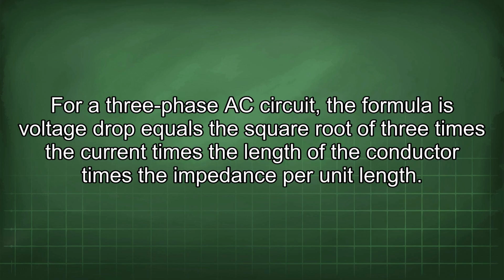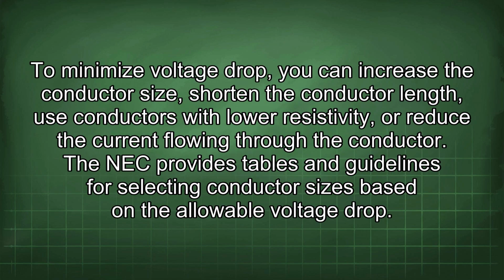For a 3-phase AC circuit, the formula is voltage drop equals the square root of 3 times the current times the length of the conductor times the impedance per unit length. To minimize voltage drop, you can increase the conductor size, shorten the conductor length, use conductors with low resistivity, or reduce the current flowing through the conductor.